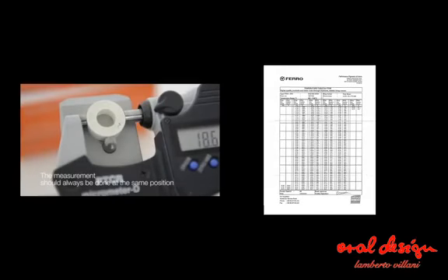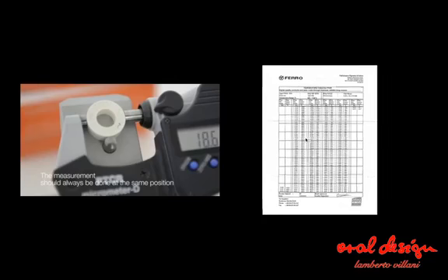you will check with a high precision caliper. You measure, and this measure here, 18.6, you are going to see on this table, it's the value. 18.6 is roughly here. You are not at 1500, but you are at 938. This is a good way to calibrate.